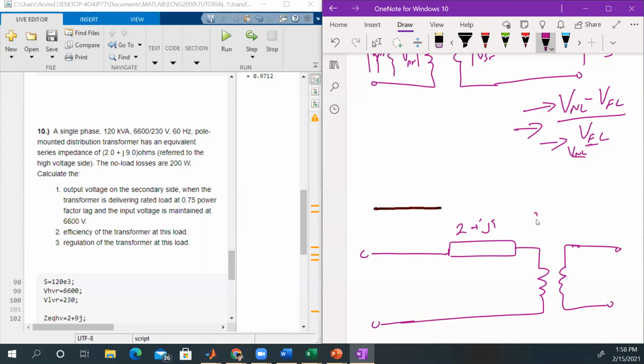We have the turns ratio 230 to 6600. Remember, this voltage you will only see if it is open circuited. You're not going to calculate these voltages at points E1 and E2 unless it is open circuited, and then you have the rated voltages. So we only use these rated voltages to calculate the turns ratio. When we put them here, that is equivalent to N1 and N2.